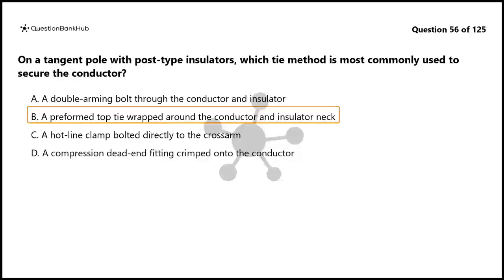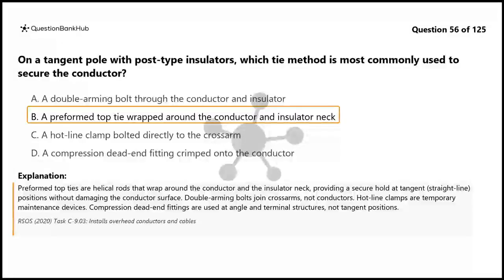The correct answer is B. Preformed top ties are helical rods that wrap around the conductor and the insulator neck, providing a secure hold at tangent, straight line positions without damaging the conductor surface. Double-arming bolts join crossarms, not conductors. Hotline clamps are temporary maintenance devices. Compression dead-end fittings are used at angle and terminal structures, not tangent positions.